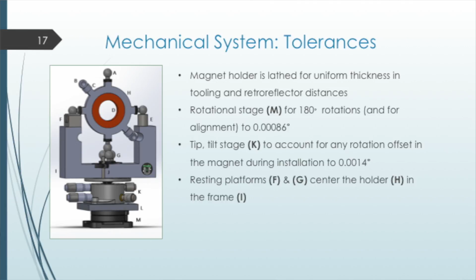Also, another thing about this frame is that it allows the holder to be rotated by 90-degree increments in all axes, which allows us to do a symmetrical analysis of the magnet, and thus determine if there's any offset errors in the system. Now, to account for any tolerances, what we've done is that we've positioned everything on top of this tilt stage and this rotational stage. The rotational stage allows us to get another degree of freedom in order to do another symmetrical analysis, except it has an accuracy which is well beyond what we really need in order to account for it.